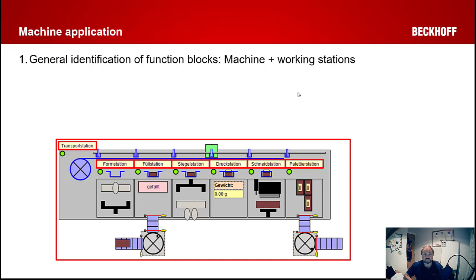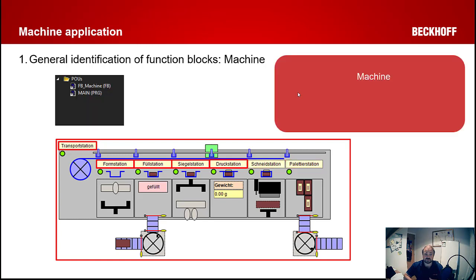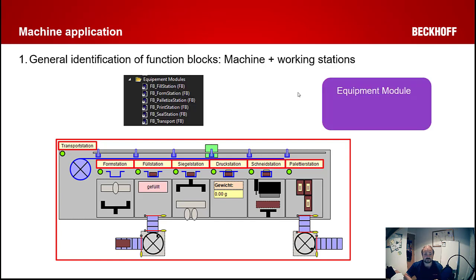Let's take a simple illustration of a machine with multiple sections: a transport system for the entire system, a forming station, filling station, sealing, weighing, packaging, and palletizing. We can break that up using the SPT framework into constituent parts. The machine part covers the entire machine — so that's the general state machine for the whole thing, the HMI interface to run and operate the entire machine, and relevant information passed up from individual substations, which are formed by our equipment modules: the transport section, forming station, filling station, etc.